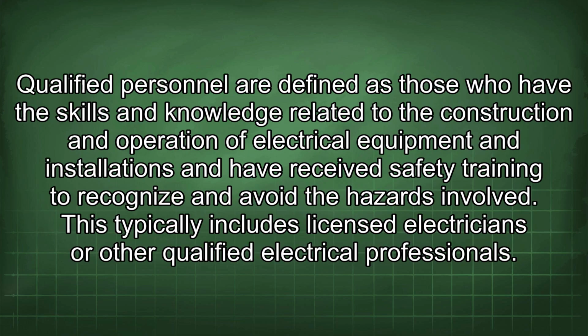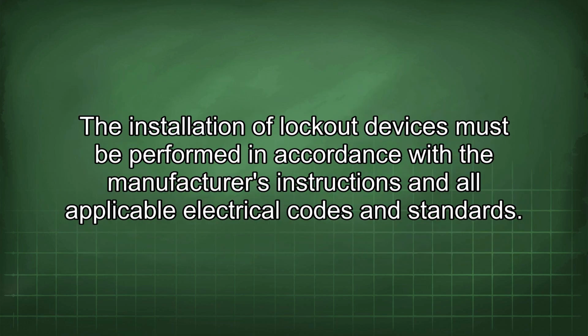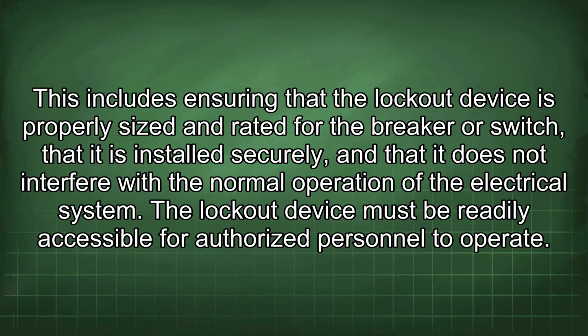Qualified personnel are defined as those who have the skills and knowledge related to the construction and operation of electrical equipment and installations and have received safety training to recognize and avoid the hazards involved. This typically includes licensed electricians or other qualified electrical professionals. The installation of lockout devices must be performed in accordance with the manufacturer's instructions and all applicable electrical codes and standards. This includes ensuring that the lockout device is properly sized and rated for the breaker or switch, that it is installed securely, and that it does not interfere with the normal operation of the electrical system.